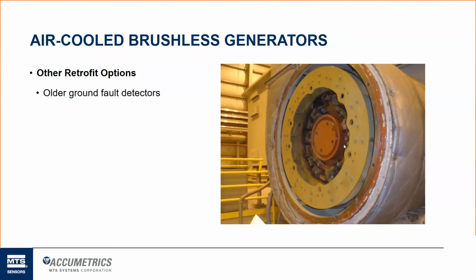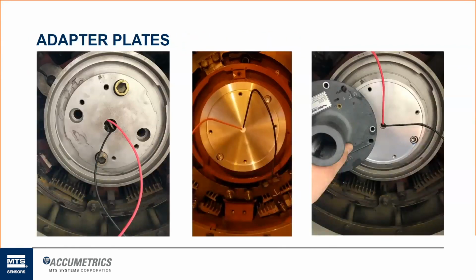So we came up with the concept of, why can't we just mount our transmitter right to the end of the shaft and just have them modify this rotor end cap by putting a small hole in the center of the end cap. That's the style that we do for many of our end of shaft systems. Here's an example of the rotor end cap that's been machined and modified with a hole in the center.